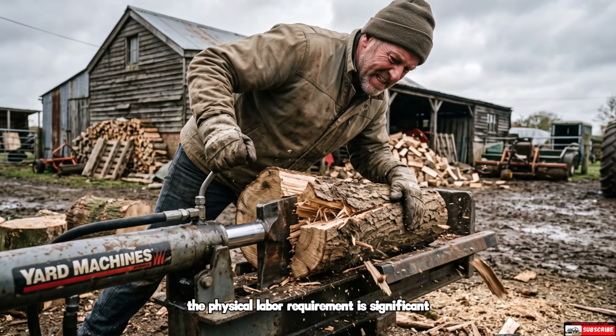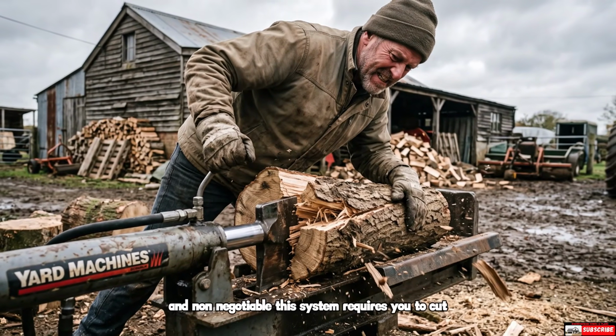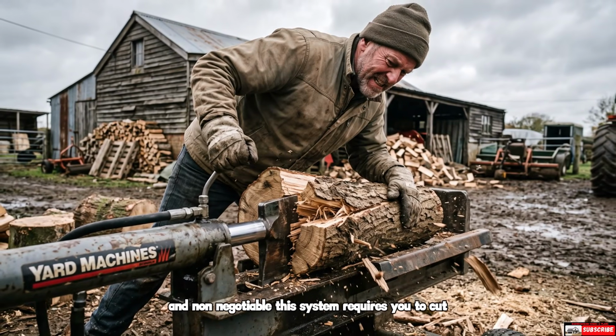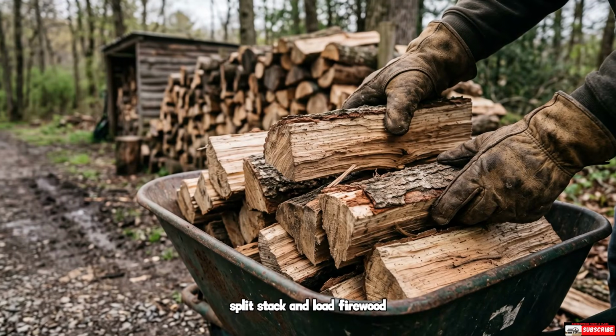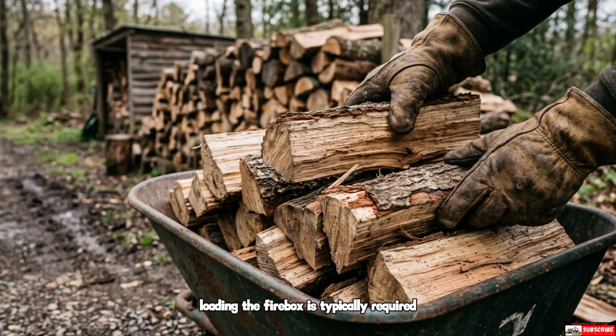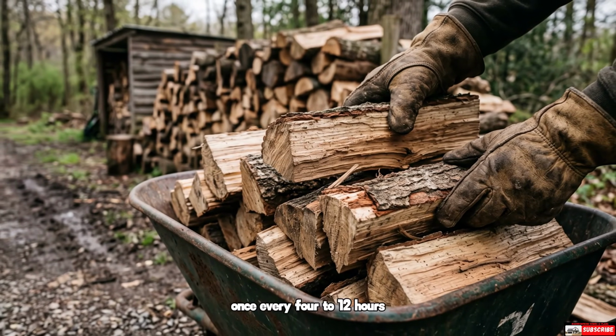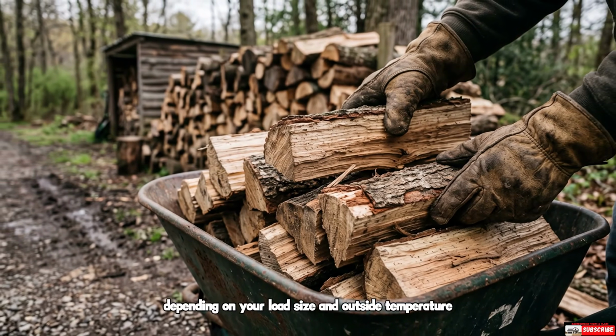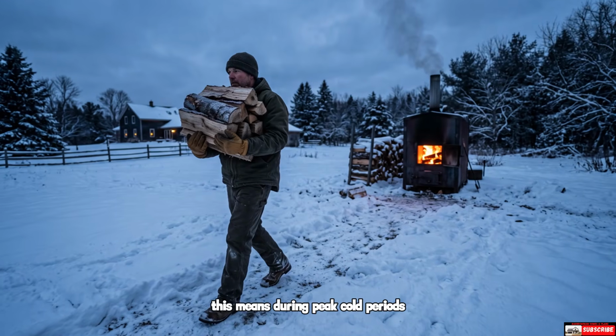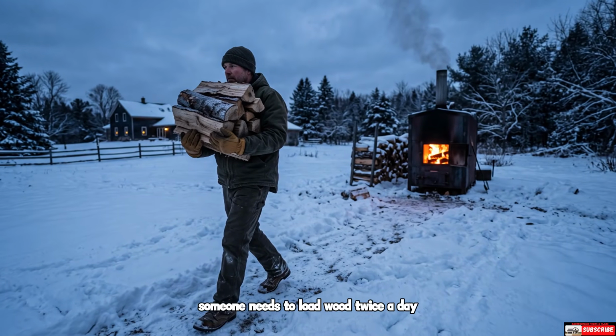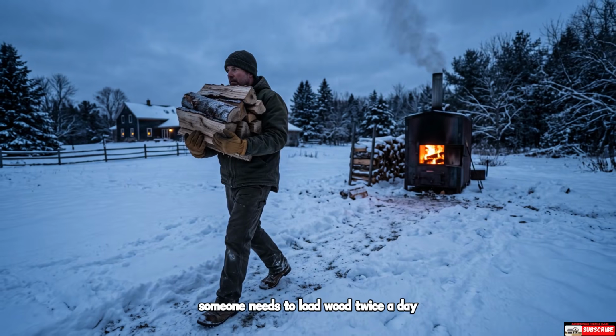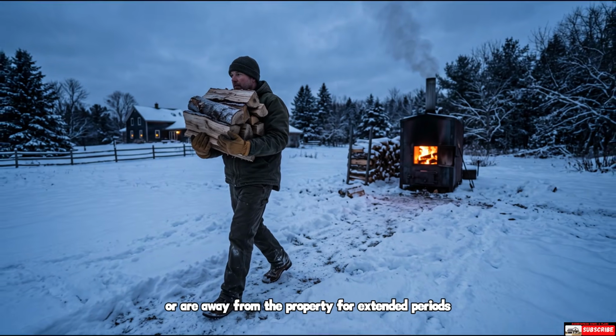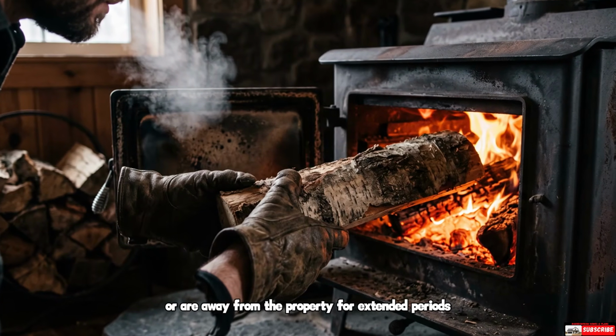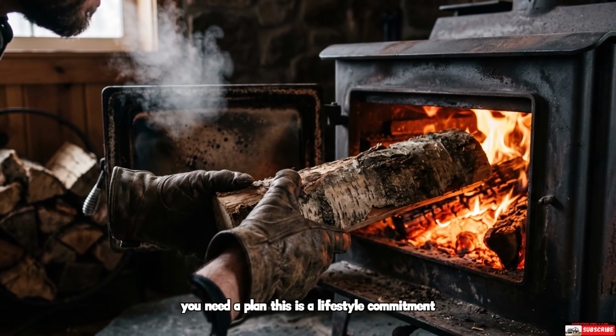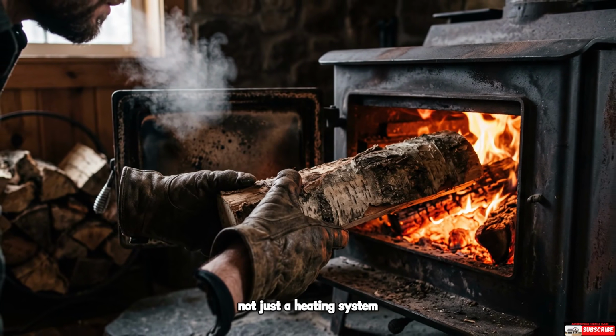The physical labor requirement is significant and non-negotiable. This system requires you to cut, split, stack, and load firewood. Loading the firebox is typically required once every 4 to 12 hours, depending on your load size and outside temperature. This means during peak cold periods, someone needs to load wood twice a day. If you travel frequently or are away from the property for extended periods, you need a plan. This is a lifestyle commitment, not just a heating system purchase.